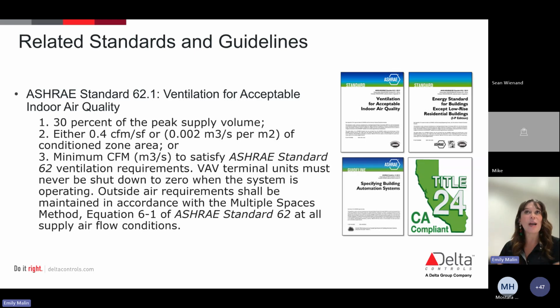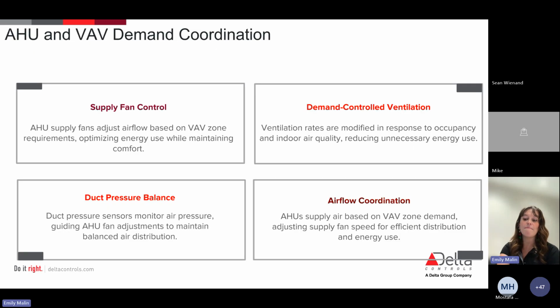So again, when we talk about why do we need a BAS system? Well, we need a BAS system because there are standards in place. Even if everybody thinks that they're comfortable, we need to be able to meet all of these. And this is how we get from point A to point B. Now, like I said, there are more and more control strategies that are coming into play. Something that we are seeing now is called demand control ventilation. Like we were talking about with VAV control, there are now some advanced operations, and one of these is demand control ventilation. Your ventilation rates are actually being modified in response to occupancy and indoor air quality. And this can actually reduce unnecessary energy usage.